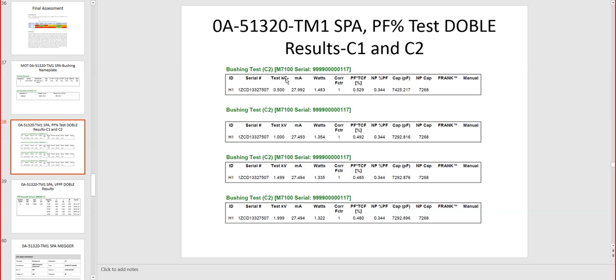different voltage. So on the same bushing that we saw before, the actual nameplate data, these are the readings for 500 volts, 1000, look at the second column, 1000 volt, 1500 and 2000. So it's, yeah, 1499 and 1999. So increasing the voltage at 60 hertz, these are the results that we found on bushing H1 according to Doble results. And then what we have here also is the C1 and C2. So we can see the capacitance, right? C1 and C2.